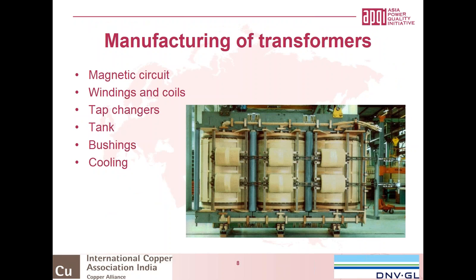If you look at what a transformer is, I've added a picture of a huge transformer in this case, not a distribution one but a huge one. There are some things which a transformer has. It must have a magnetic circuit. Also, it has some windings and coils, and some transformers do have tap changers. You will see that the transformer has a tank and also bushings and some cooling.